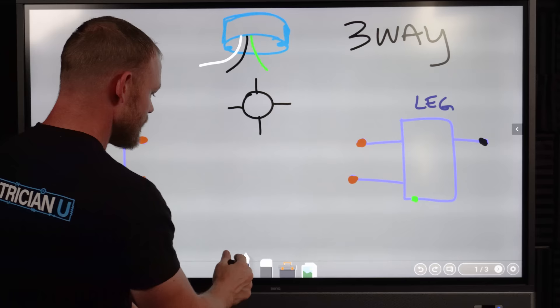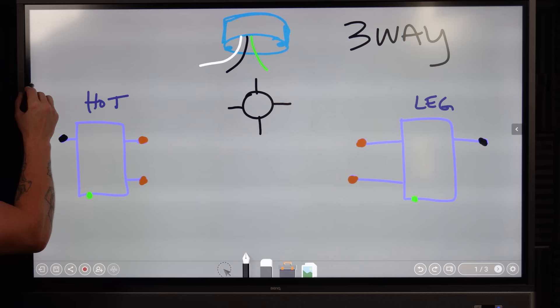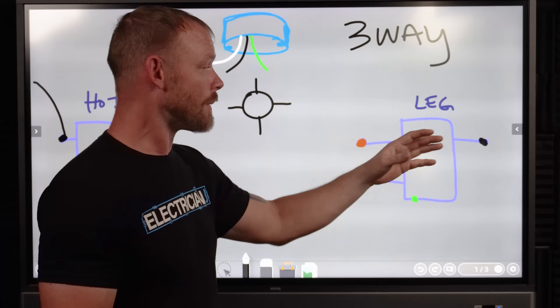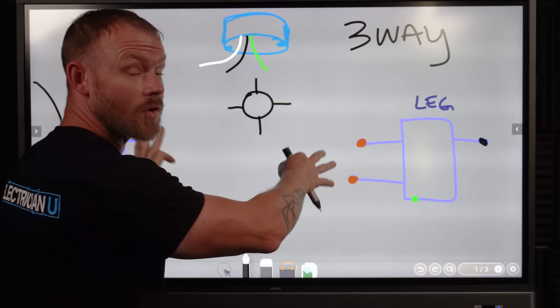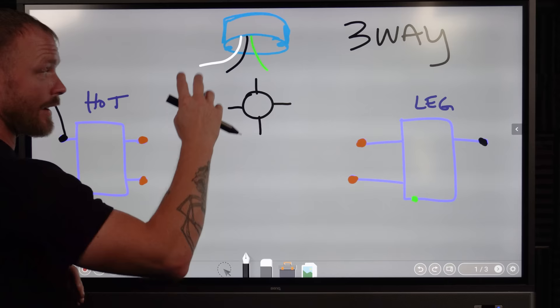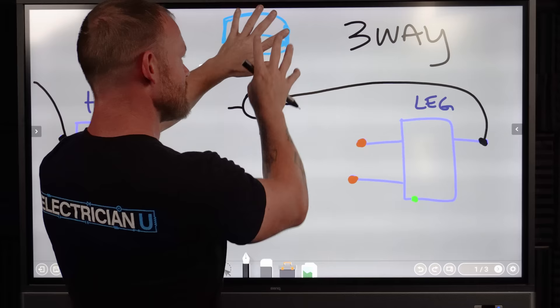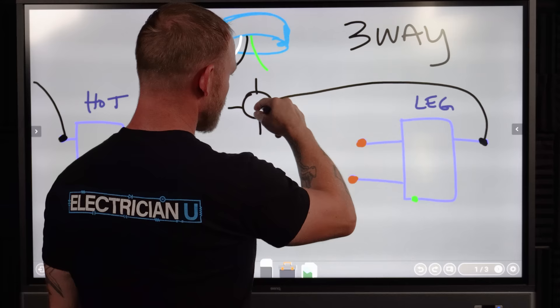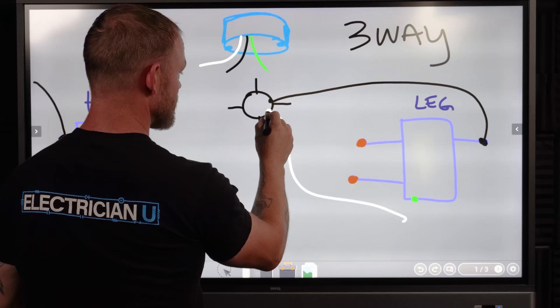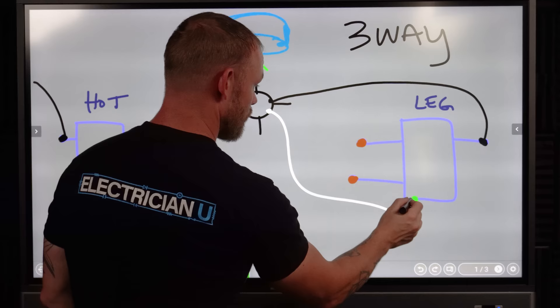How a three-way switch works: we have our incoming power — an incoming hot coming in. We always hook that up to the black screw. On the leg side, the wire going up to the light source is also on the black screw. Notice the gold screws in between — those are your travelers. The weird ones, the hot or the leg, are always going to be on your black terminal. On this side you'd have your leg going up to the light. The black would go there, and in this box somewhere you have a neutral going to it and a ground going to it.